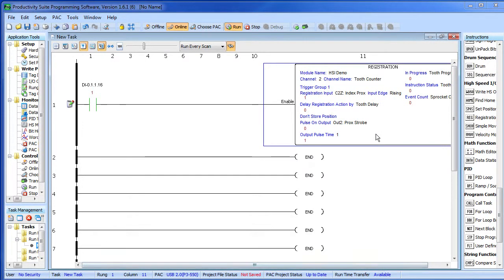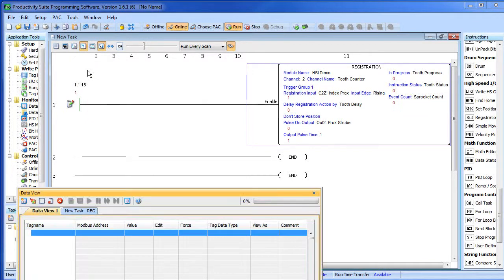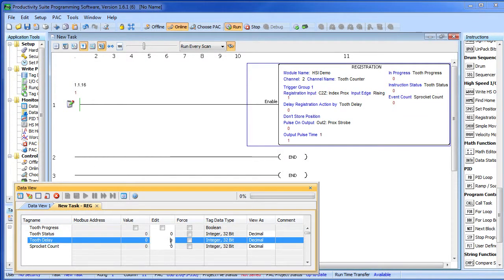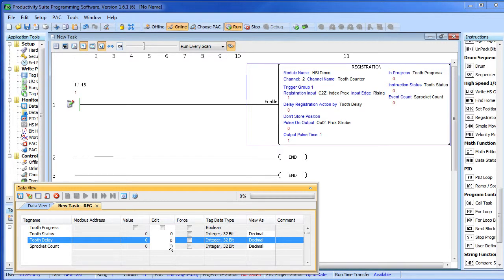Before we get started, let's do one more thing. I'm going to go back in this instruction and say monitor – that's going to create a data view for me and monitor all those tags we created. Let's bring up our data view so we can see those tags. We know we can't have a delay of zero so I'm going to put in a delay of 30 teeth and write that out. I'm going to flip switch 16 on my input simulator and now I see that my instruction is running because my in progress flag went to a 1.